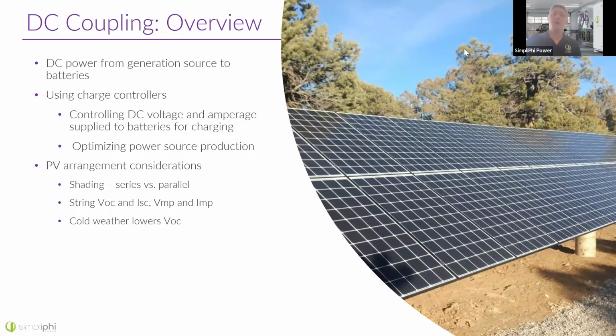DC coupling, as an overview, is when you generate DC power and charge the batteries with that DC power. You're going to need a charge controller that's going to control the DC voltage and amperage that's supplied to the batteries. And it's also going to optimize your power source production. So a charge controller is monitoring the voltage that the PV array sits at and how much power it's producing in total. And it's always going to make slight changes to those conditions to try to get it to produce more power. We'll talk a little more about how that works.